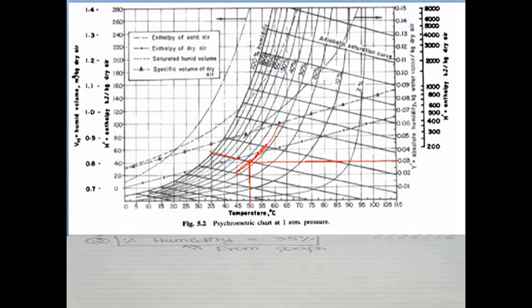Second step, draw the line of 35 degrees Celsius on the WBT axis. Which one is the WBT axis here? From 100% humidity, the inclined lines are called WBT lines. In this figure, the red inclined line indicates the WBT line, at nearly 35 degrees Celsius. These two lines intersect at one point. The intersection point lies between the percentage humidity curves of 30% and 40%.